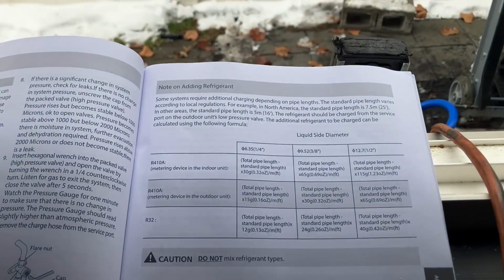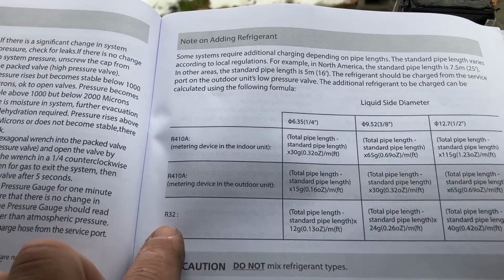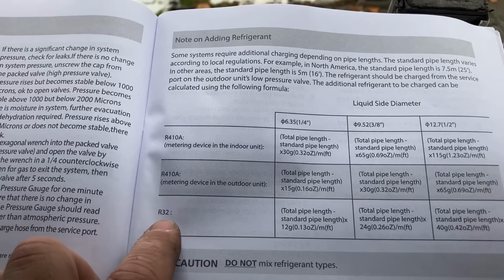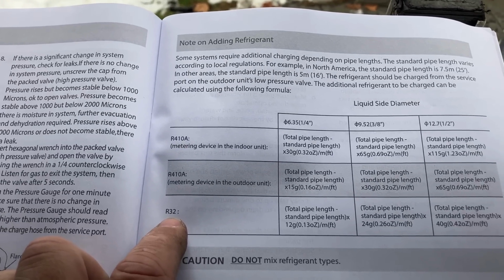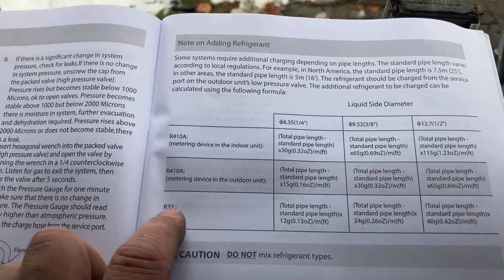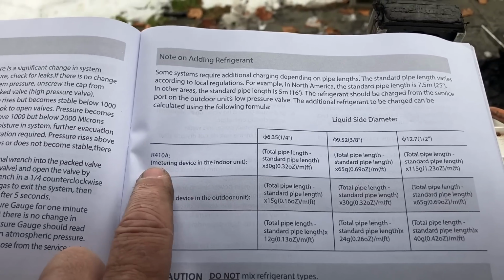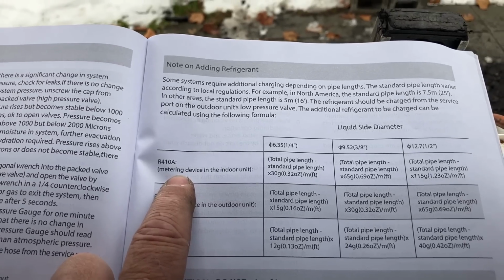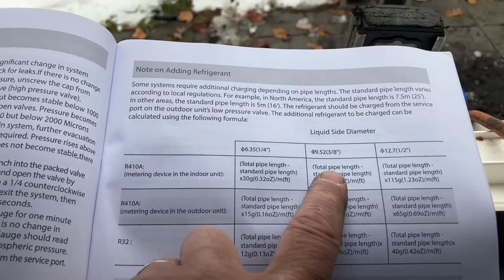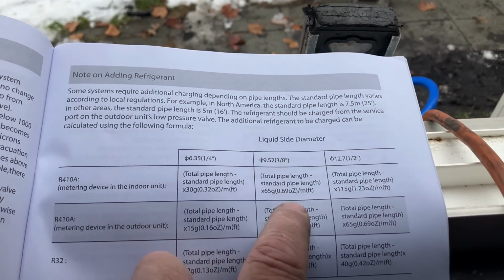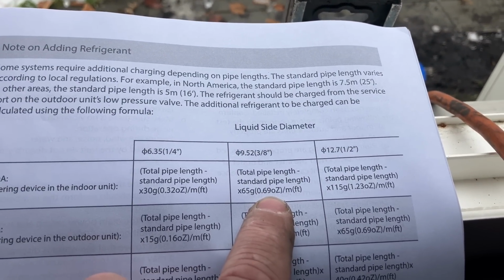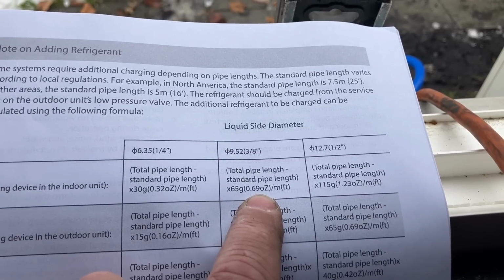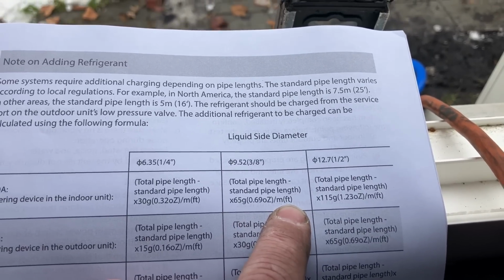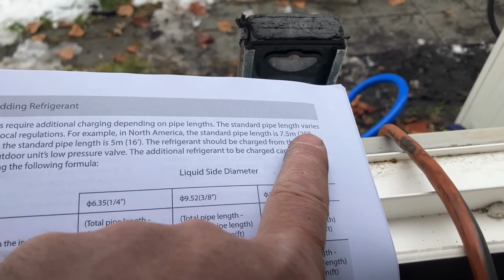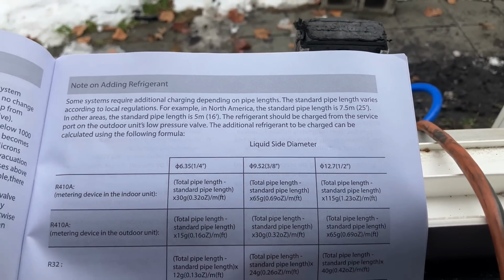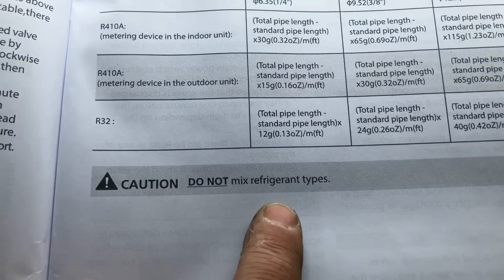Now, utilizing this page, it gives us a hint that looks like Senville will be switching over to R32 from R410A once they deplete their stock and start manufacturing new equipment. But our metering device is on the inside unit, because that's that EEV, that electronic expansion valve. And our liquid line diameter is 3/8. So we're gonna need to add 0.69 ounces, or almost 0.7 ounces for every foot over 25 feet. Now we have roughly 25 feet of line set, so we're good. And of course, never mix refrigerant types.